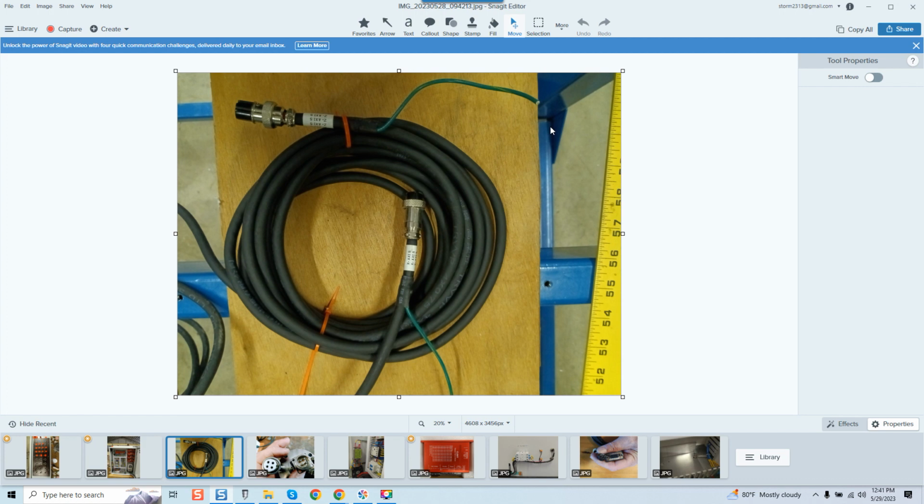If you see cables that are custom built or built by another vendor, and they are not clean and symmetrical in the sense of the build that they are, and you find external wires attached, you need to question that person or that vendor and find out why that was done, because this is not best practice. In best practice, a commercial grade cable would have all of the leads terminated within the plug. You're not going to see external leads just hanging out abruptly.